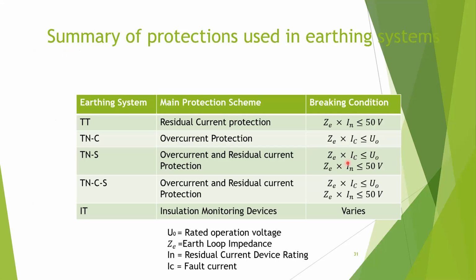And in a TNS system, we can have both of these breaking conditions. So we can have RCD and overcurrent. So that is what is mentioned here. TNCS, RCD and overcurrent, similar. These two offer similar protection. And an IT system does not have a breaking condition because we are valuing the continuity of operation. So it does not have a breaking condition, but we have insulation monitoring devices. So if there is an insulation fault, we are going to see it on an insulation meter. Okay, so those are the things you should know about earthing systems.